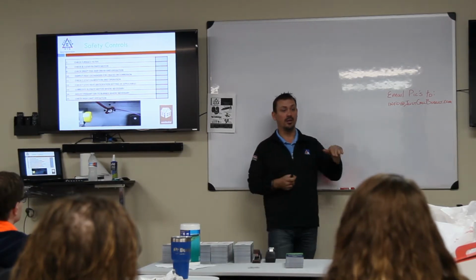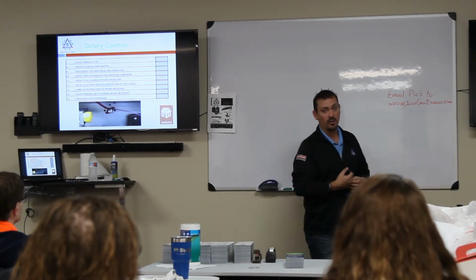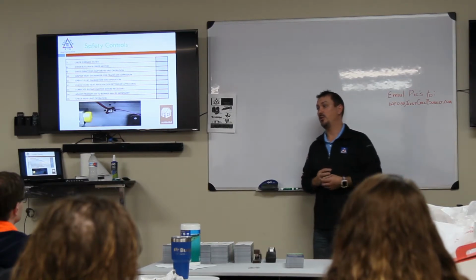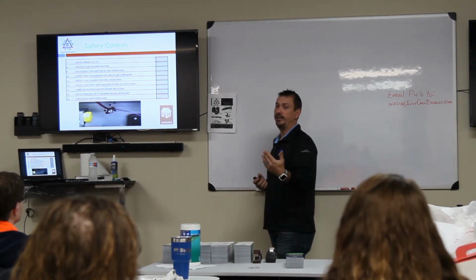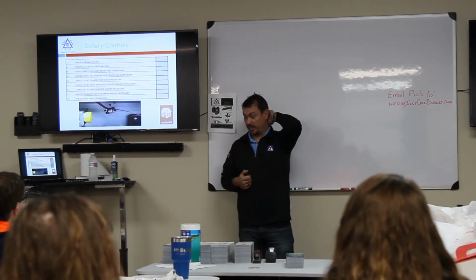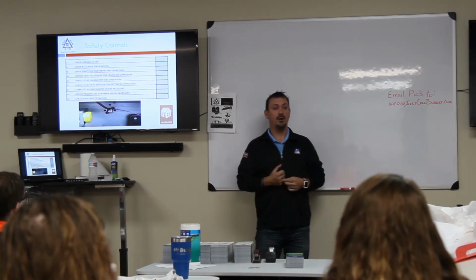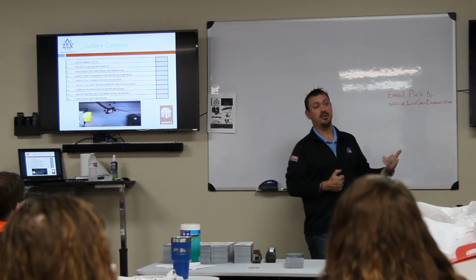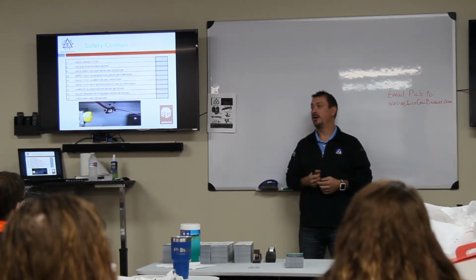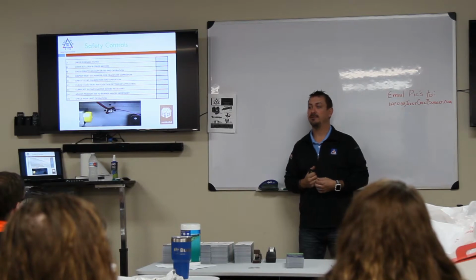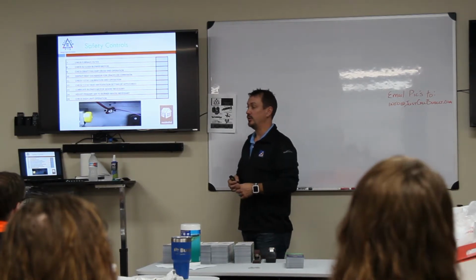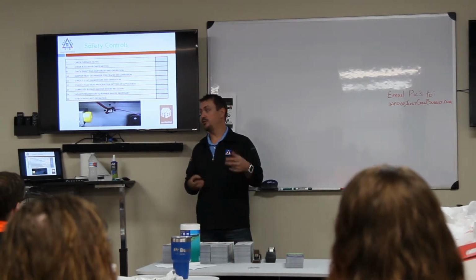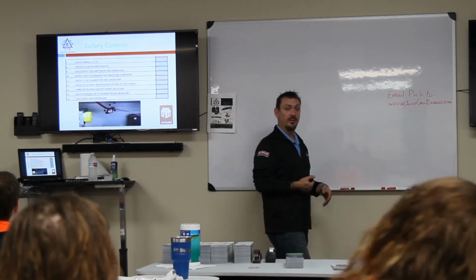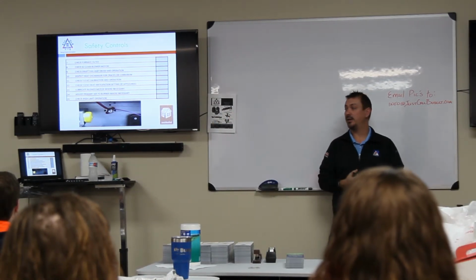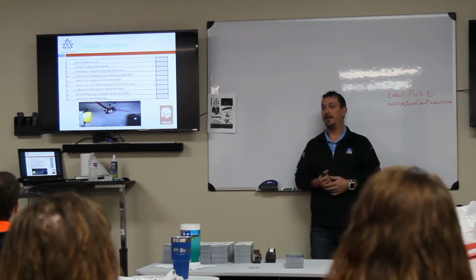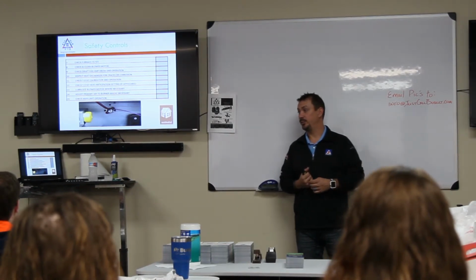If I'm getting really close to that, then I'm going to want to start inspecting my flue to make sure that it's clean and clear. If I'm running it through a chimney, make sure that there's no debris in there. And of course, if I'm running it through a chimney, I better have a flue liner, so make sure of that. If there's lots of bends and things like that in there, that can affect the pressure on that inducer. Making sure there's nothing blocking it. If it's a 90%er, make sure of the same thing. Make sure there's nothing blocking it, that maybe there's no mud dauber nest or anything like that in the flue pipe.